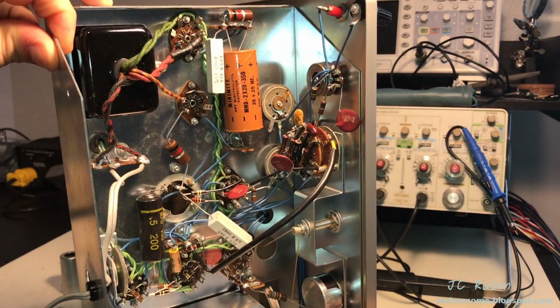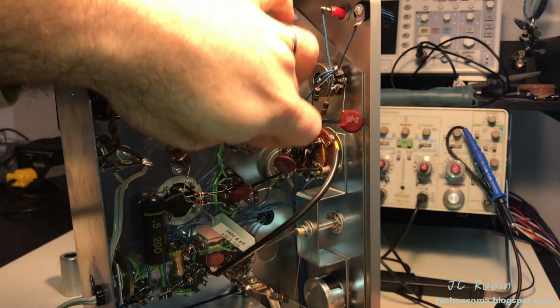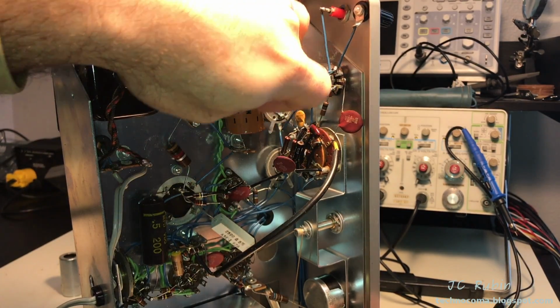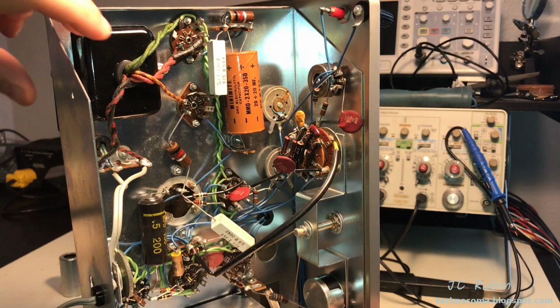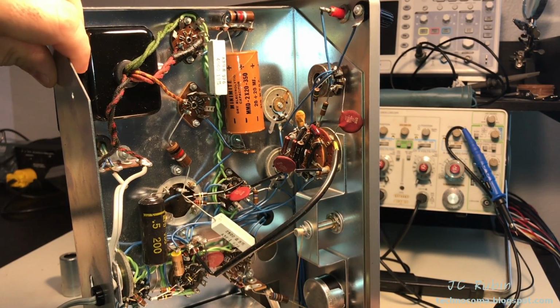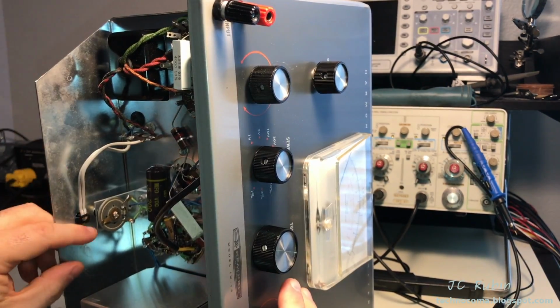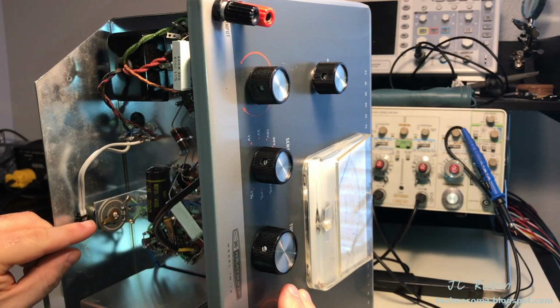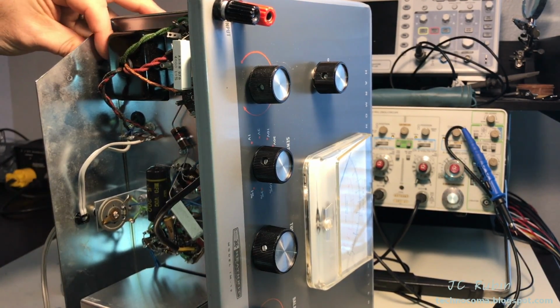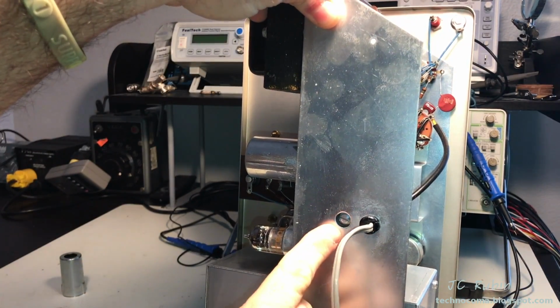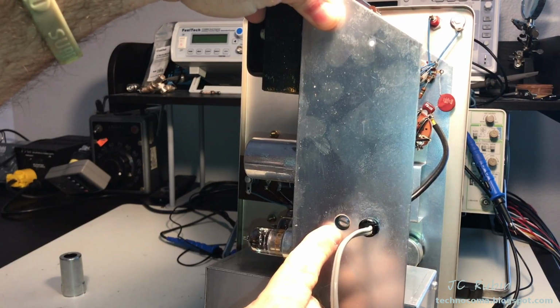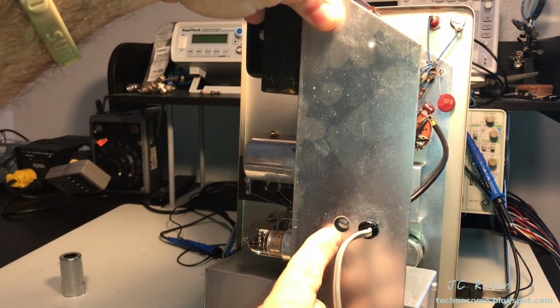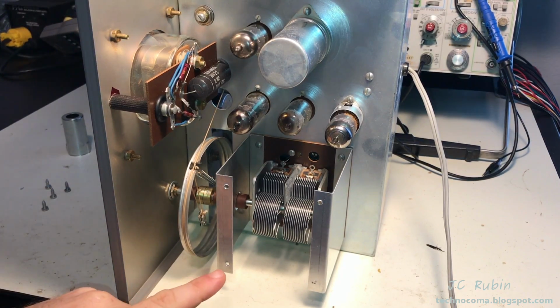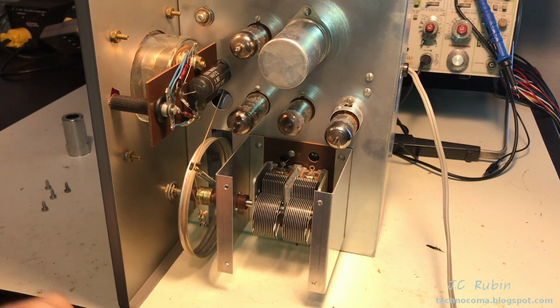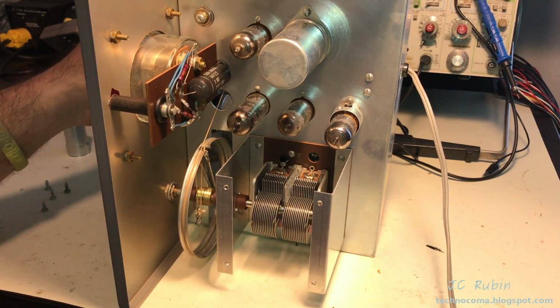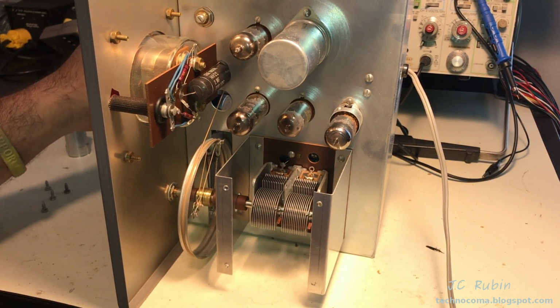We can also see, if we look in here, there are a couple of wire-wound potentiometers not available on the outside of the unit. It looks like for the purposes of internal calibration. I'm sure that will reveal itself in the manual as part of the calibration procedure. Another one of those wire-wound calibration potentiometers also sits on the rear of the unit. However, this one is exposed and can be adjusted from outside the unit, but it's designed that it doesn't have a knob on it. It's part of the calibration setup, but could be done with the box closed for whatever reason. Opening the top portion of the shielded area reveals only the open air capacitor for tuning. We can see that if I turn the tuning knob, it's just the open air capacitor. So there's nothing much more to see under there.